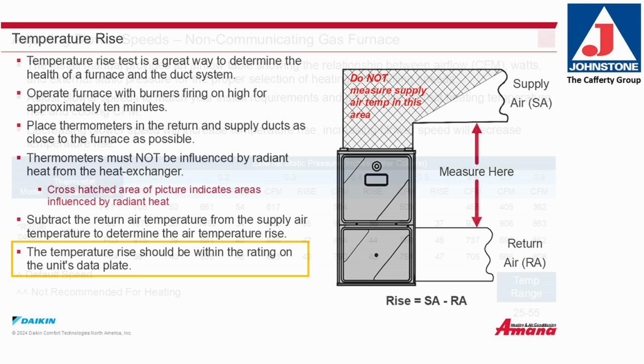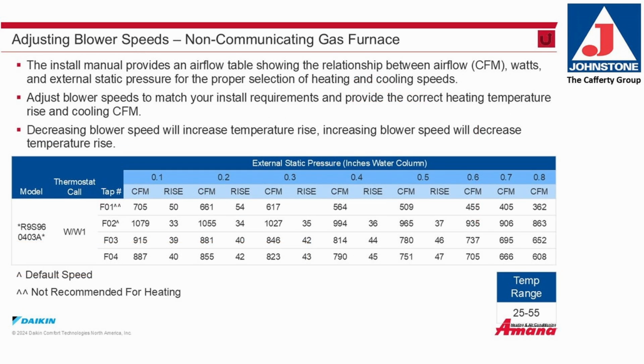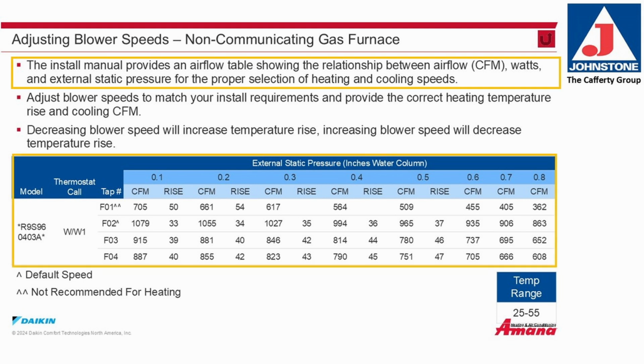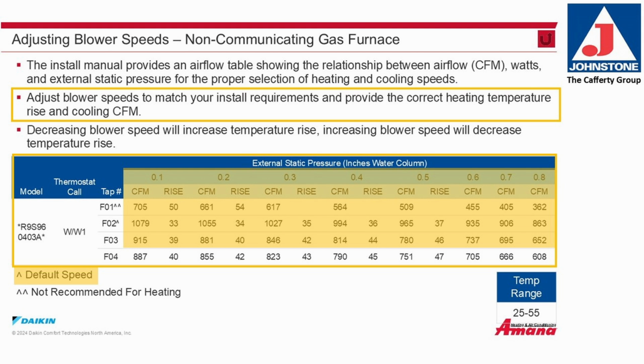Adjusting the blower speeds on a non-communicating furnace. The installation manual provides an airflow table showing the relationship between airflow in CFM, watts, and external static pressure for the proper selection of heating and cooling speeds. Adjust blower speeds to match your install requirements and provide the correct heating temperature rise and cooling CFM. Decreasing the blower speed will increase temperature rise. Increasing the blower speed will decrease temperature rise. Refer to the chart for the correct CFM and temperature rise at the applicable external static pressure. Temperature rise range should be 25 to 55 degrees Fahrenheit.